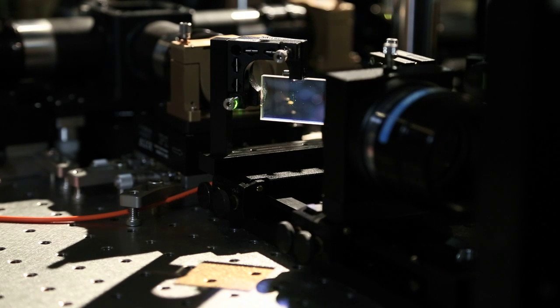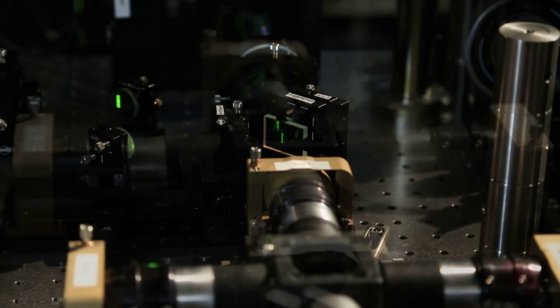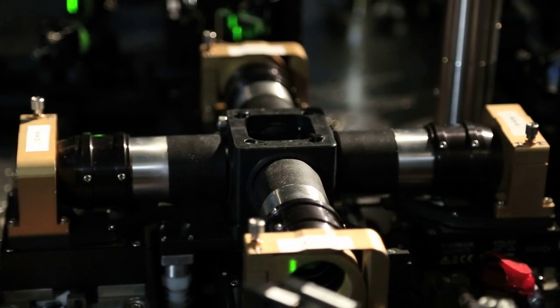Then at that point, we have a dichroic mirror in the beam path. It's a beam splitter, so it takes the illumination beam, directs it towards the objective. And now, through the objective, we finally get to the sample.